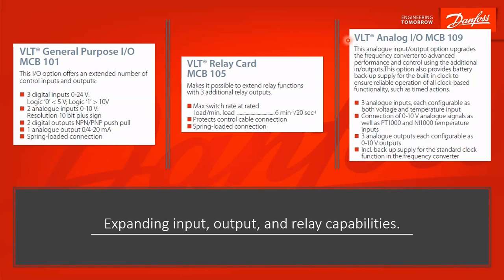The analog input-output, MCB109, gives you an additional three analog 0 to 10 volt inputs that can be configured to take temperature sensors. It gives you three additional analog outputs, and it includes the backup battery supply for the real time clock. Without this, if you set a time and date into the drive, every time you cycle power it will revert back to its default settings. So if you want to use the real time clock, get the VLT analog input-output MCB109 option.